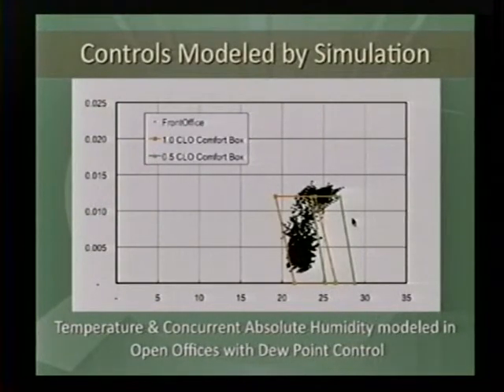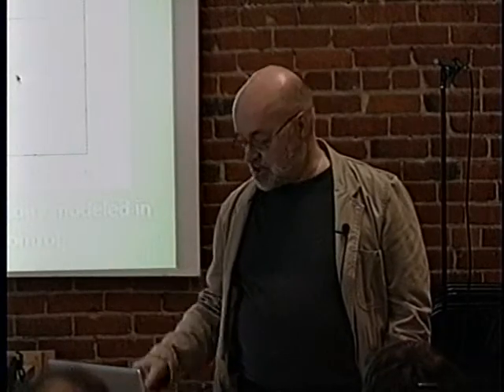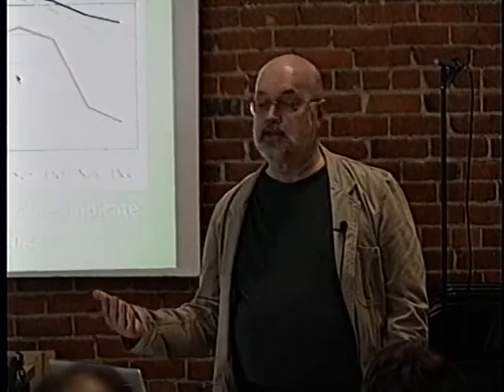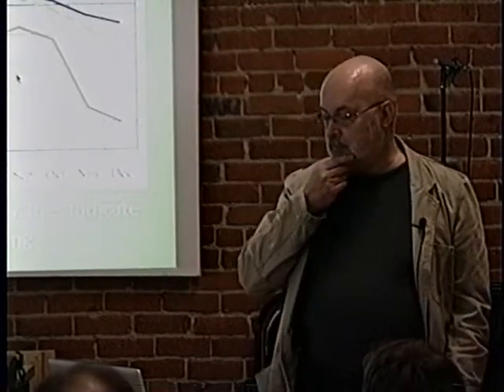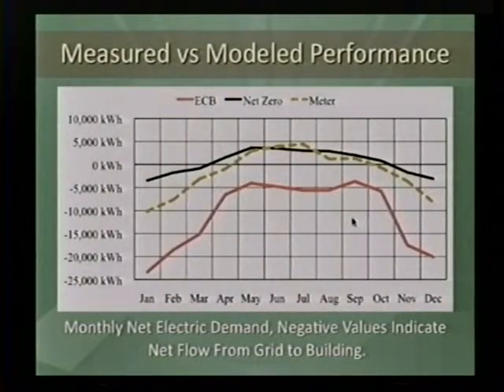Our time steps on this building in the simulation were 5-minute time steps. We've gone down to 1-minute time steps. And in terms of controls, we'll use the temperature from the previous time step to make a control decision in the current time step to initiate a piece of equipment dumping energy into the space or removing it from the space. And so we will get very detailed in simulations where we feel it's necessary, and we'll go back and do measurements afterwards. This is the first year graph of the measured and modeled performance.